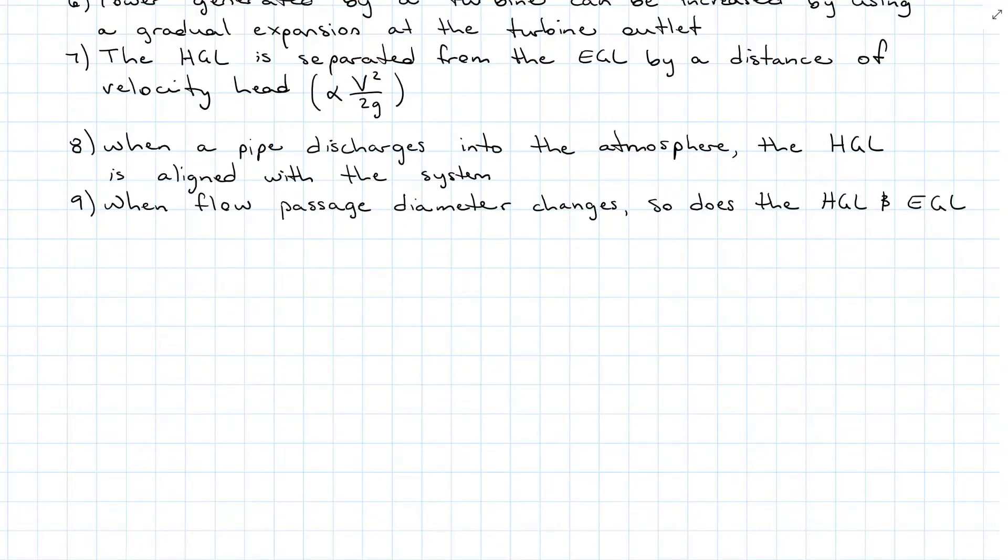When the flow passage diameter changes, so will the grade lines. If the hydraulic grade line falls below the pipe line, the pressure head is negative, and that can indicate potential cavitation.